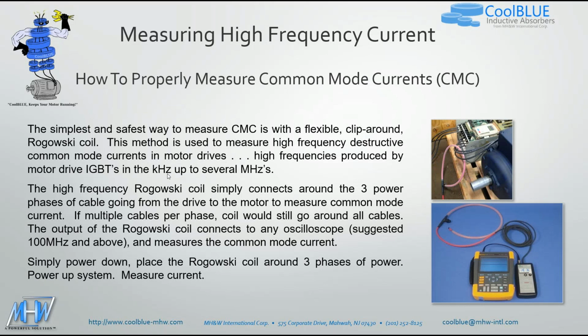The high-frequency Rogowski coil simply connects around the 3 power phases of the cable going from the drive to the motor to measure the common mode current, as shown here in the picture. If multiple cables per phase, the coil would still go around all cables. So if each phase had 2 conductors, you'd then put it around all 6 cables.